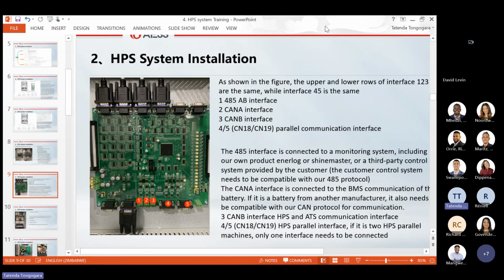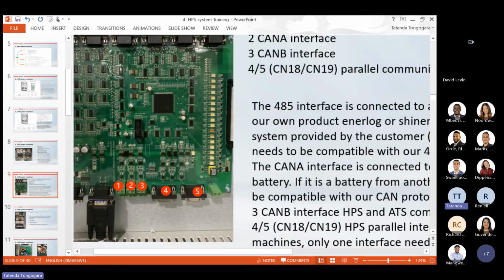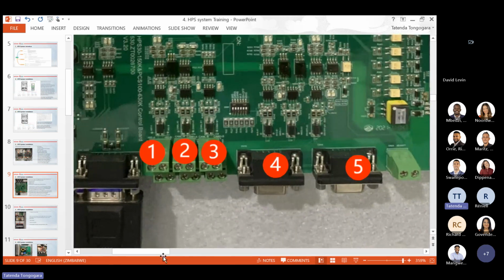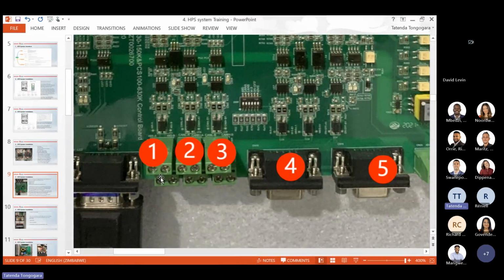Okay, sorry about that. So I was explaining the RS-485 interface where you connect your monitoring, and then CAN A, that is number 2. Let me just zoom in so that everyone can see. So this is our RS-485, labeled here on the control board, and then we have CAN A. CAN A is dedicated for the BMS only. And then CAN B, if you have your ATS in the system, or if it's on the PCS, you have your bypass, you connect it here.